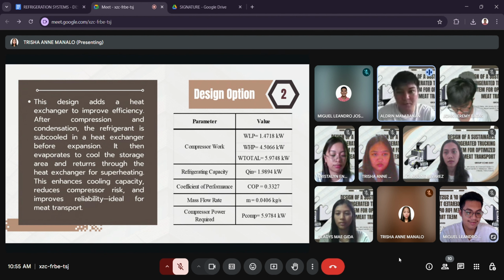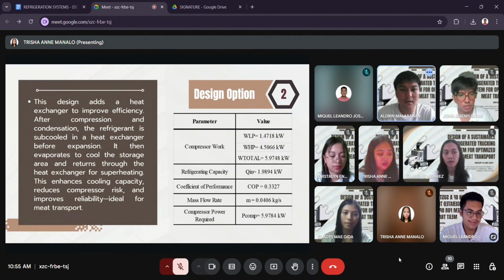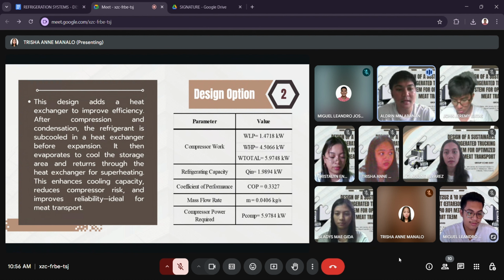Design option 2, vapor compression cycle with heat exchanger. This design adds a heat exchanger to improve efficiency. After compression and condensation, the refrigerant is subcooled in a heat exchanger before expansion. It then evaporates to cool a storage area and returns through the heat exchanger for superheating. This enhances cooling capacity, reduces compressor risk, and improves reliability, ideal for meat transport.